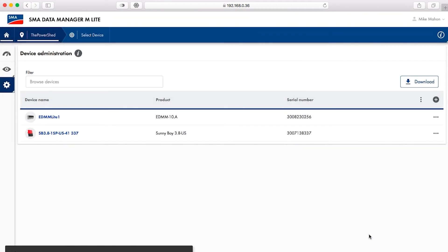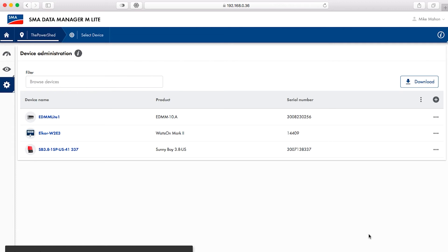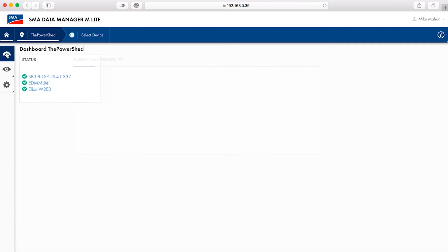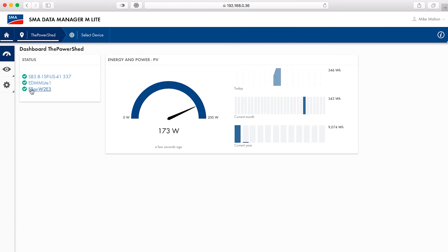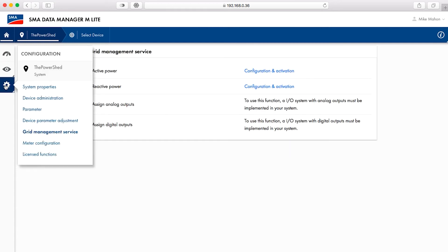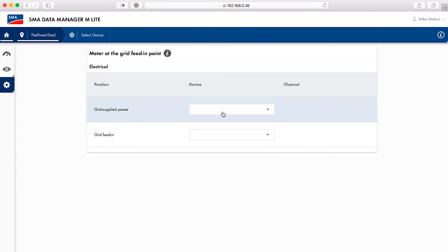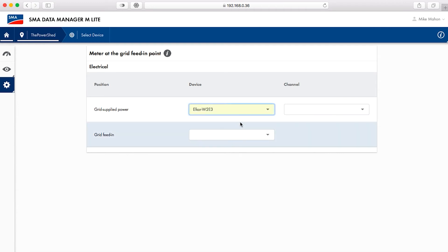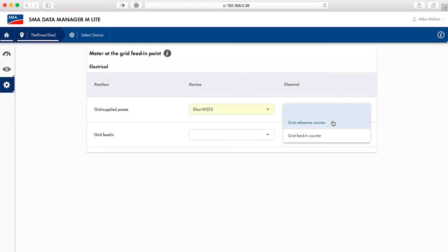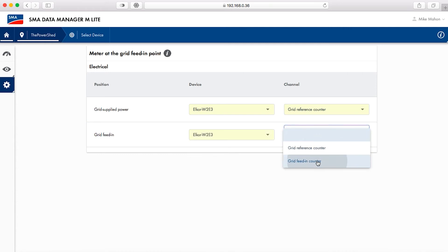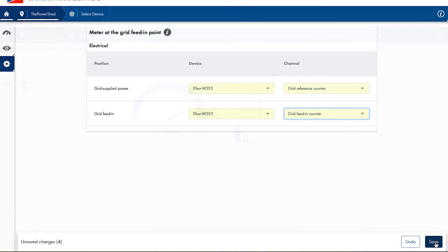After the meter shows up in the list in the device administration window, click the plant dashboard icon. Verify that the meter appears in the status list with a green checkmark next to it. Select the configuration icon from the menu on the left and select meter configuration from the menu. On the screen that appears, select the meter in the device column for both purchased electricity and grid feed-in. Select grid reference counter in the channel column for purchased electricity. Select grid feed-in counter in the channel column for grid feed-in. Click save when done.